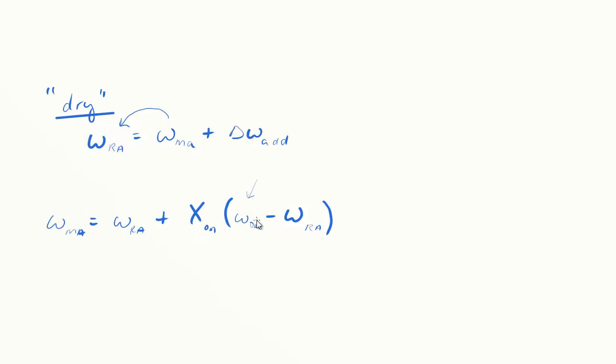If the outdoor air fraction is 1, when you distribute this, you'd get 1 of the OA and this cancels with this. The nice thing is we know that value, so we actually have two equations and two unknowns. We don't know mixed air and we don't know return air, but we have two equations, so we can solve for the return air.